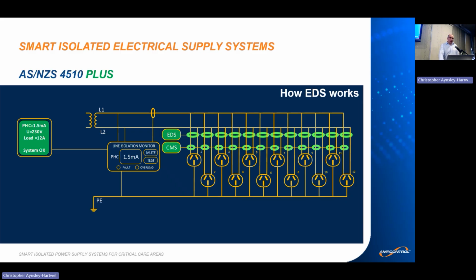And just a few slides to explain how EDS works. EDS stands for Earth fault detection. We know that an earth fault is responsible for an increase in prospective hazard current. So what happens if we have an earth fault in the system? It will result in an increase of prospective hazard current, and the line isolation monitor will detect it and trigger an alarm. And then the line isolation monitor will go into EDS mode. In EDS mode, it injects an earth fault locating current. And this current, you see the dashed line, will go back to the line isolation monitor via the earth fault. And because EDS uses current core balance current transformers, they will detect this earth fault locating current and send information to the information panel that current is detected on circuit number 10.